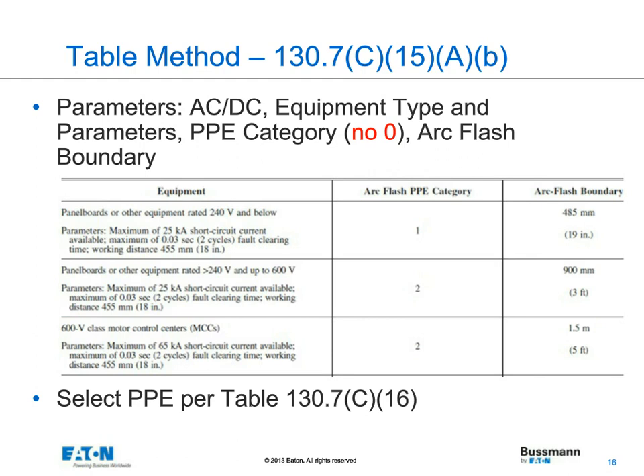It's very important to understand that when we developed these tables, we being the NFPA 70E committee, looked at these parameters, which include things such as available short circuit current, opening time, and working distance. All of these parameters affect how we arrived at the associated arc flash PPE category. So, for instance, if it was a panel board 250 volts or less, you'd have to meet those parameters, and if you met them, you'd have a PPE category of 1.